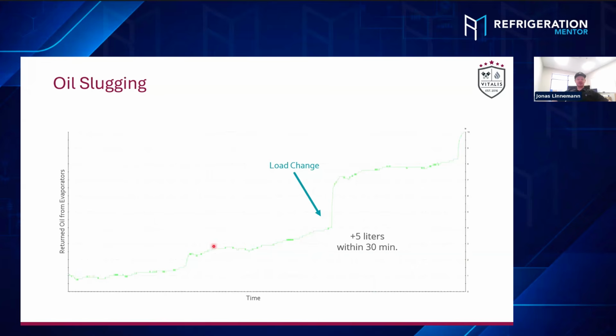And yeah, that's another picture out of the field when finally one of these oil slugs you want to prevent by proper design basically comes back to the system. So we have built in a field a little oil accumulator in the suction line and monitored the oil level just to see how the oil behaves in the returning suction line. And here you can see it's pretty steadily rising and rising. But then out of nothing, we have seen an additional 5 liters within 30 minutes. And that's basically of load changes or such a big oil slug gets whipped out of an oil trap in the field piping.